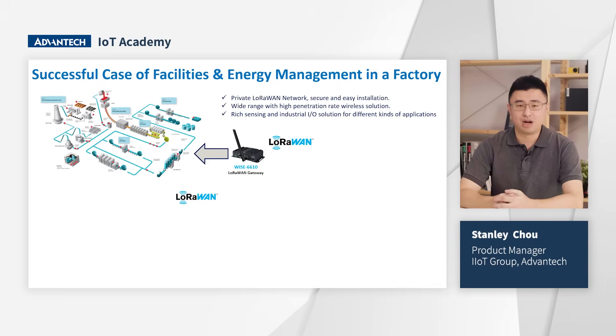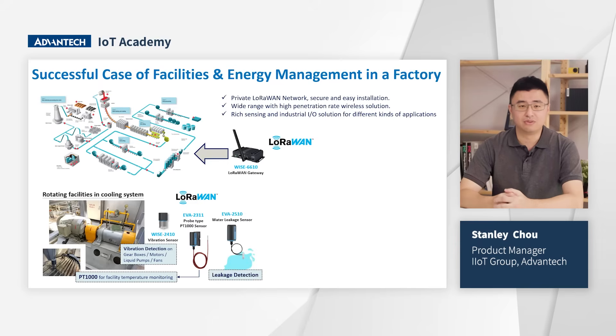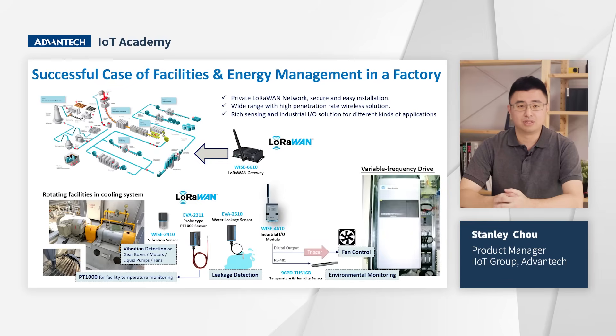For factories, customers are establishing private LoRa networks using Advantech solutions to ensure data security. They use the WISE 2410 to monitor the health status of conveyor motors, gearboxes, pumps, and fan motors for critical manufacturing equipment. They also employ the EVA 2311 RTD sensor for temperature monitoring and the EVA 2510 for leakage detection. Furthermore, they connect environmental temperature sensors with the WISE 4610 to monitor variable frequency drives — if the temperature exceeds a threshold, the system sends a command to activate cooling fans. They also integrate energy meters with the WISE 2200-A RS485 module for remote access to energy consumption data.